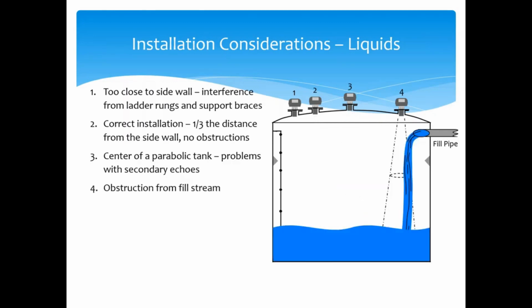And then number 4, you're doing okay until you start to fill. This is something that might happen intermittently. It's not a fixed obstruction that's always there; sometimes you have flow, sometimes you don't. When you have flow in that pipe, you're going to pick it up, and we're going to tell you, hey, our level's way higher than what it truly is. So you never want to mount in the fill path inside of a tank.